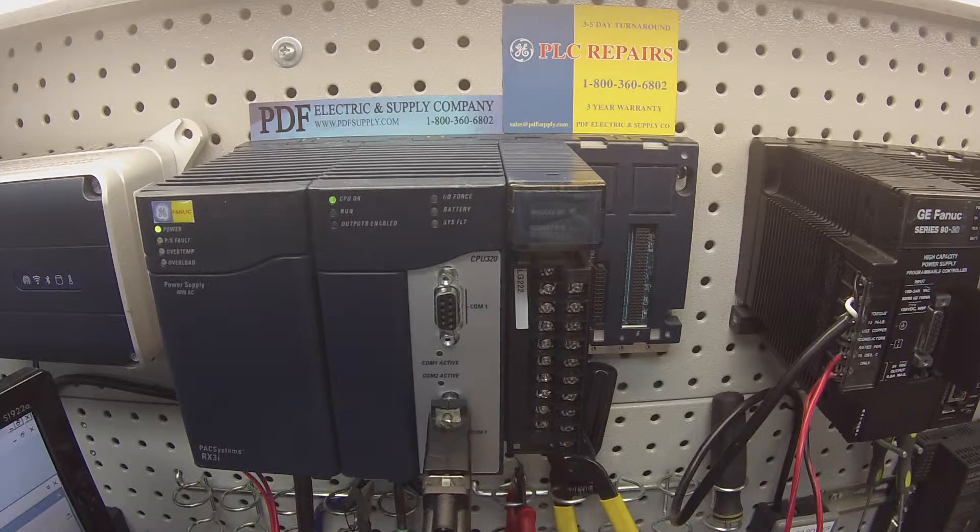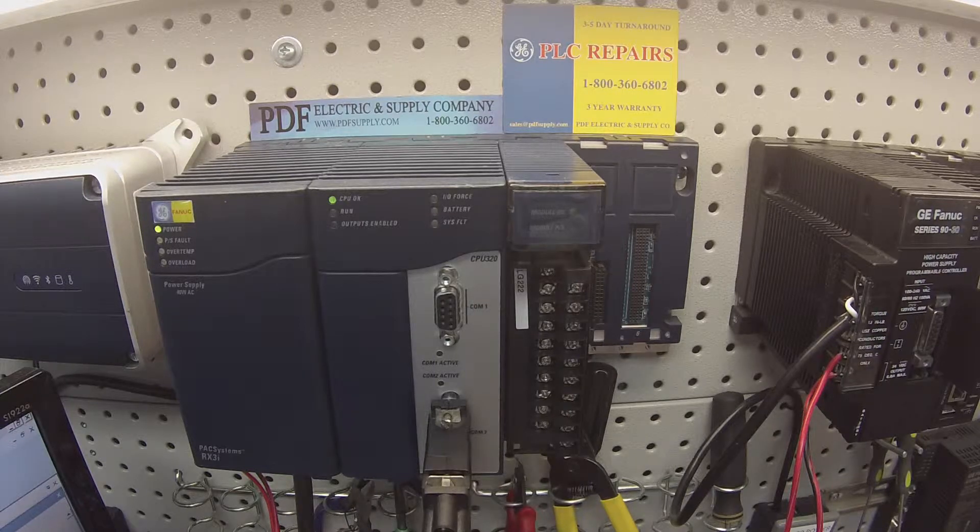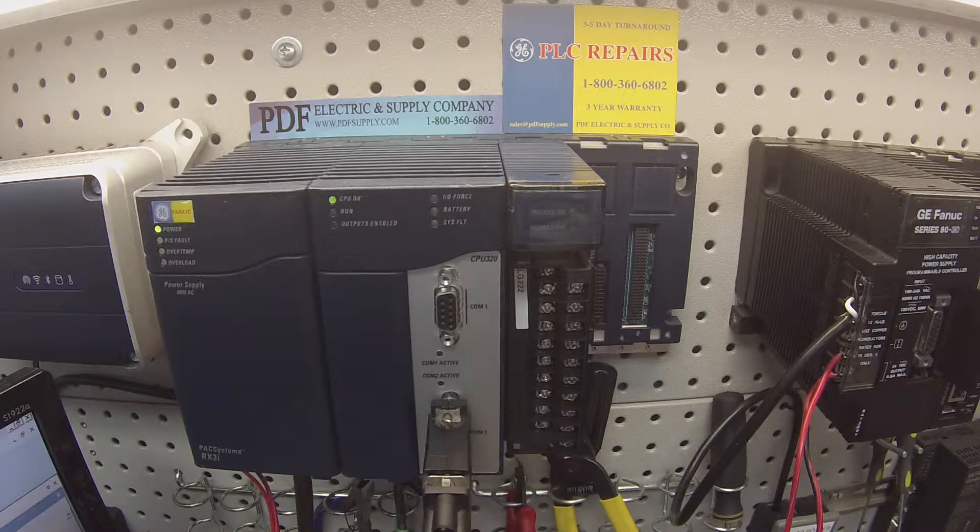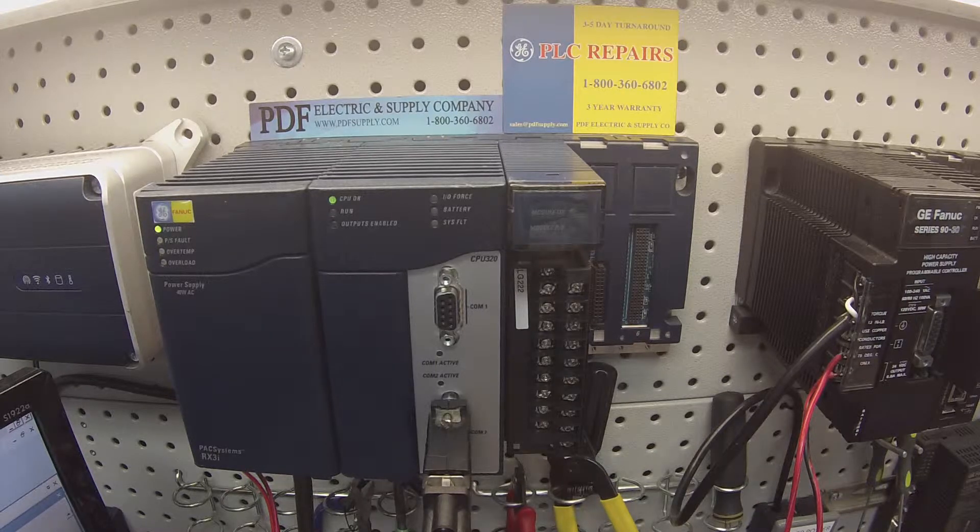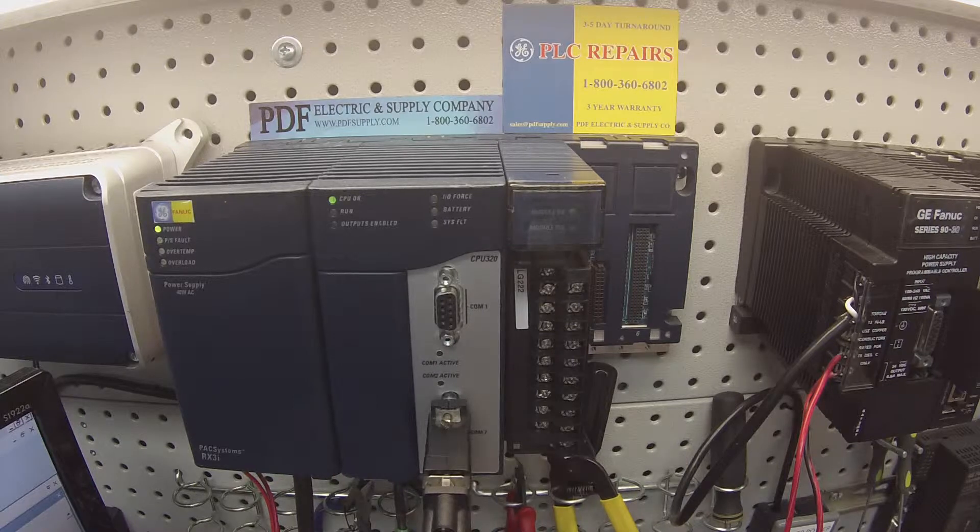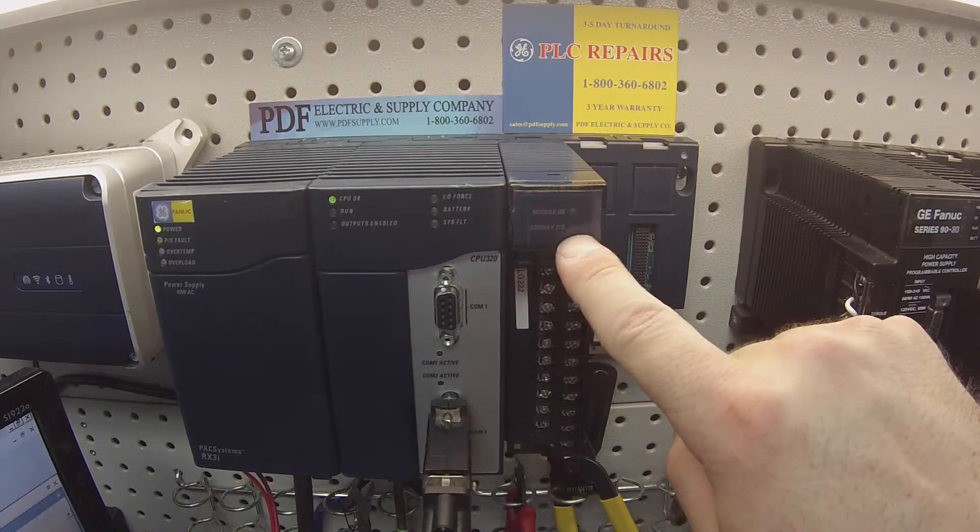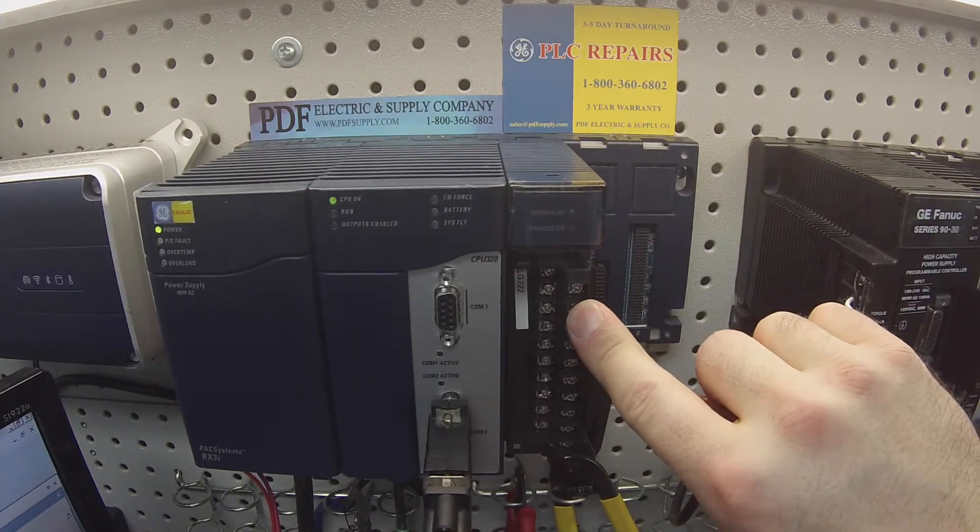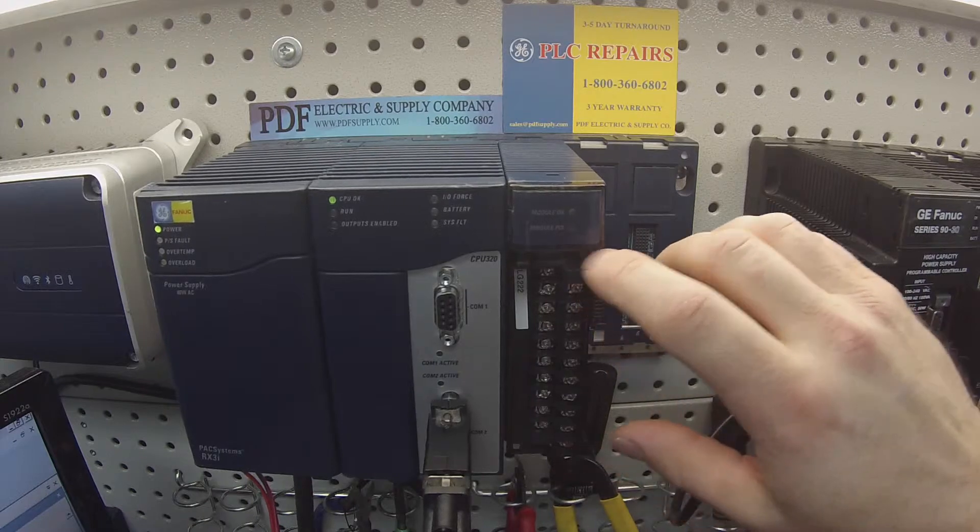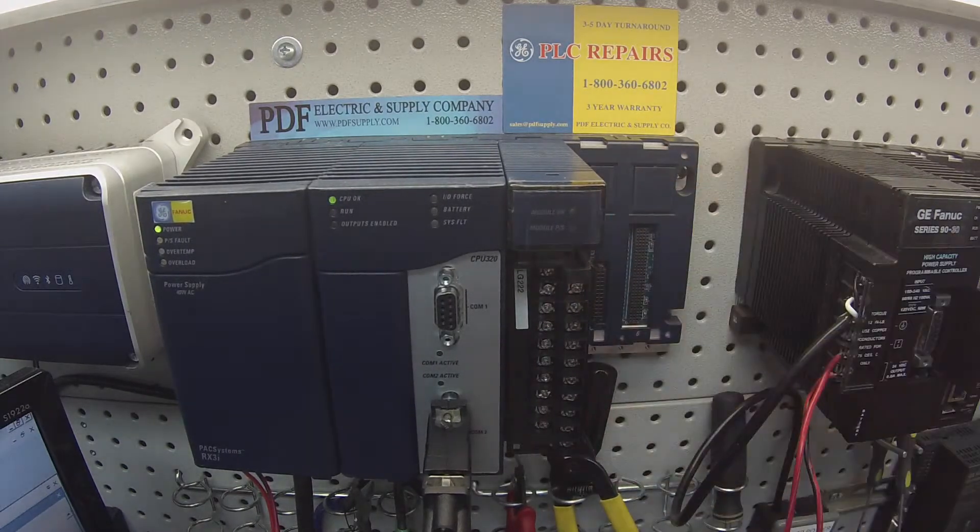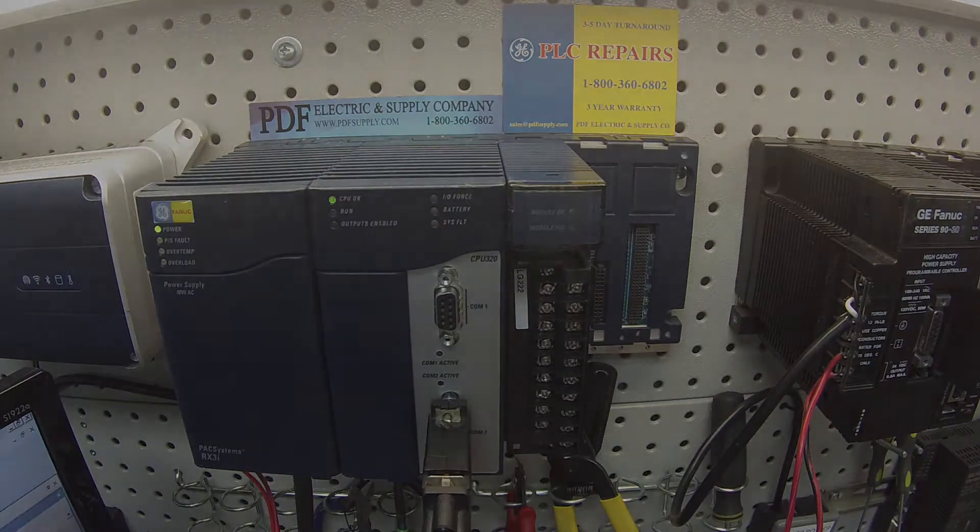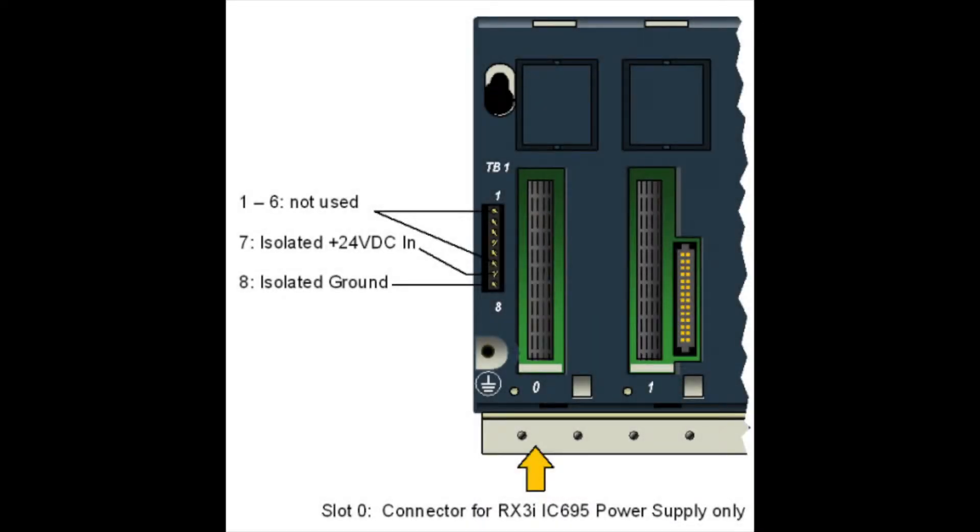I'm using an IC695CHS007 7-slot rack. You can use a 012 12-slot rack or a 016 16-slot rack, whichever you choose. You need to know that this other LED, the module power supply that powers this individual unit, needs to come from an outside source and be connected to the rack. You must have this in order to do this test.